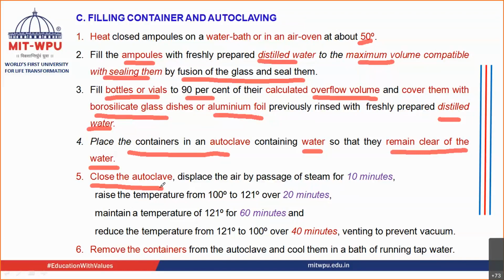And then, in the first 10 minutes, you are going to displace the air that is present in the autoclave by the passage of heat. In the next 20 minutes, you are going to raise the temperature of that autoclave from 100 to 121. In the next 60 minutes, you are going to maintain the temperature at 121 degrees Celsius.